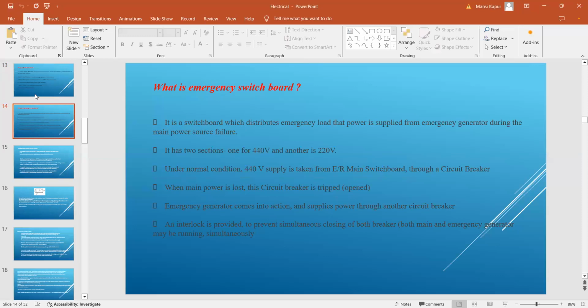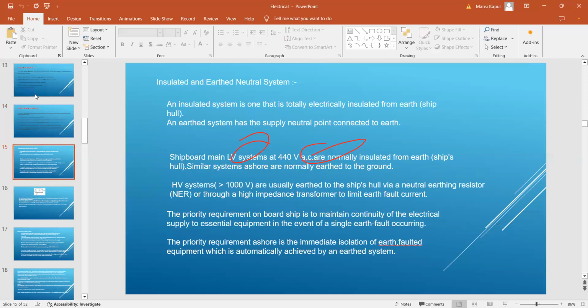So what is the emergency switchboard? It is a switchboard which distributes the emergency load. That power is supplied from the emergency generator during main power source failure. It normally has two sections. One section is 440 volts for running your machineries, and 220 volts for your lighting and small motors. Under normal condition, 440-volt supply is taken from the main switchboard through a circuit breaker. When the main power is lost, the circuit breaker is tripped, the emergency generator comes into action and supplies power to another circuit breaker. An interlock is provided to prevent the simultaneous closing of both breakers, because both main and emergency generators may be running simultaneously. That is why they have provided an interlock between them.